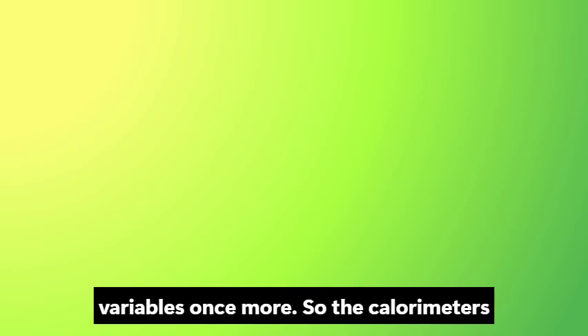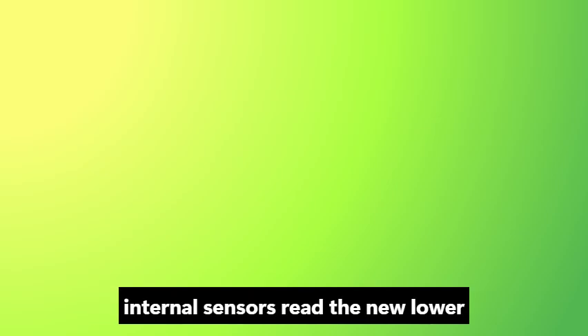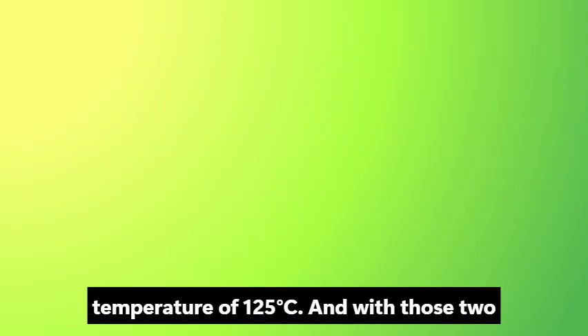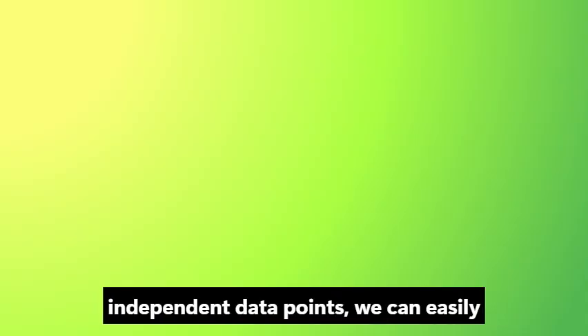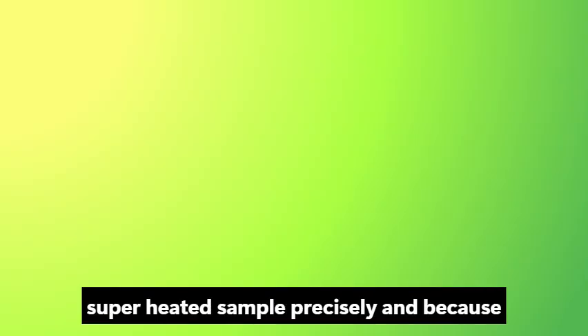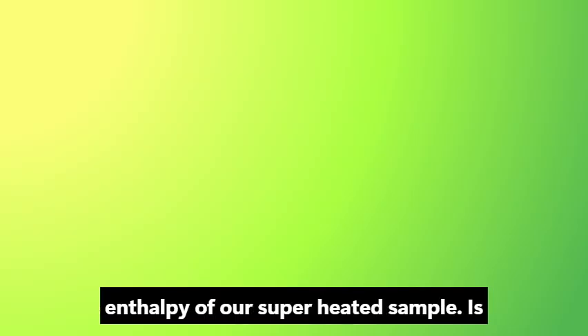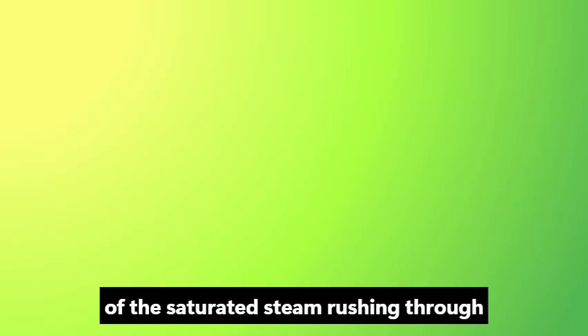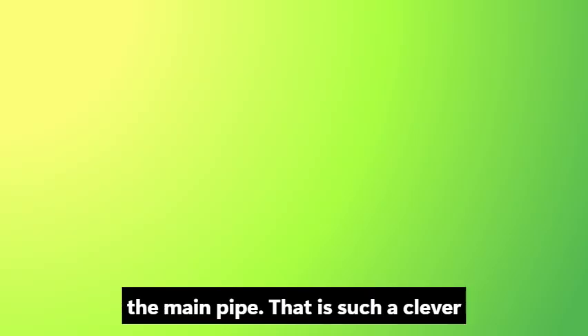So the calorimeter's internal sensors read the new lower pressure at 100 kilopascals and a new temperature of 125 degrees Celsius. And with those two independent data points, we can easily pinpoint the specific enthalpy of that superheated sample. Precisely. And because the entire expansion was isenthalpic, the enthalpy of our superheated sample is mathematically identical to the enthalpy of the saturated steam rushing through the main pipe.